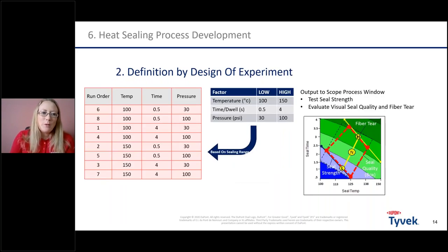There's another method among several different ones - design of experiments. When you have statistical software, you indicate your presumed low and high conditions in terms of temperature, dwell time, and pressure. The software will propose combinations of those parameters and a run order. Then you can produce packages and test them again, for example the seal strength, with visual evaluation and maybe also fiber tear.